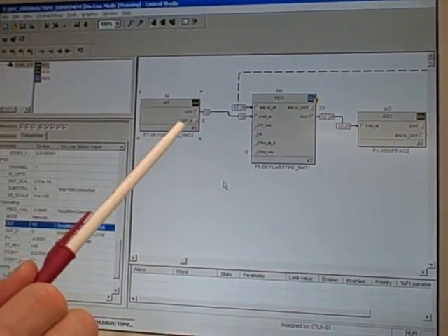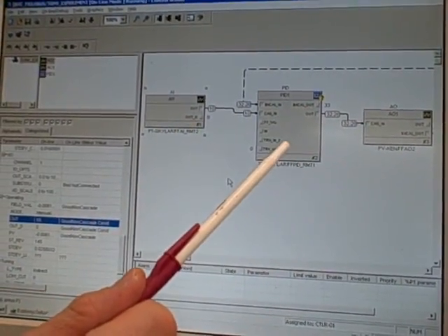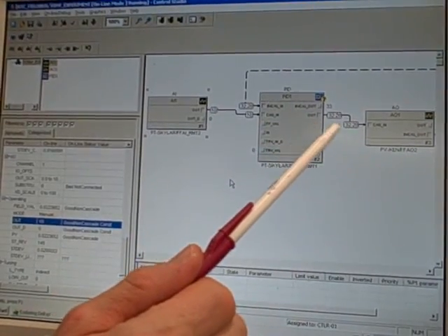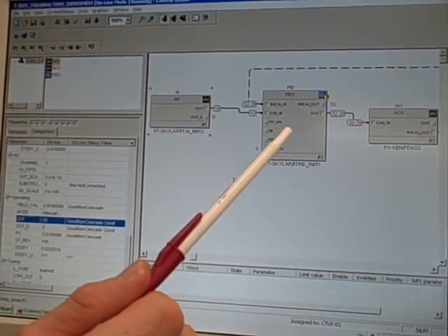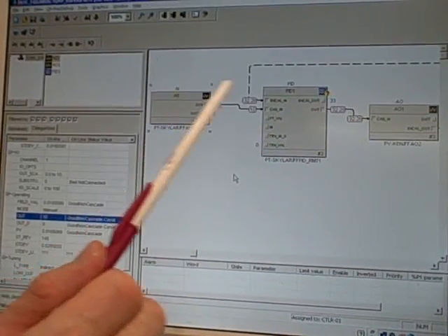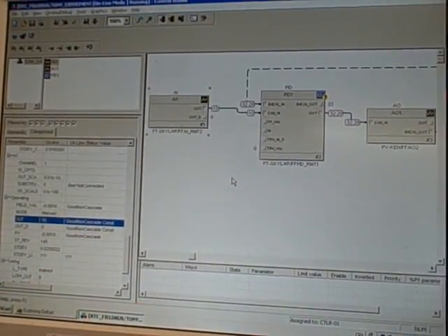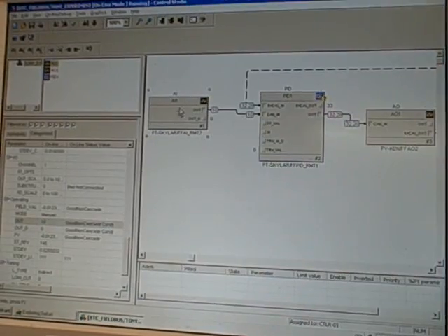Again, we're used to seeing something like this when it comes to PID, setting the output of a PID block to whatever value we want it to be. However, in Fieldbus, you have the freedom to do that with any block you look at. So switching this back, for the analog input block, I can go back to automatic mode.